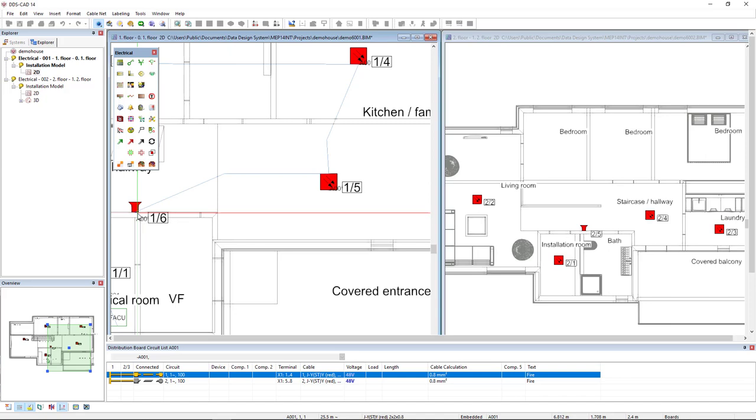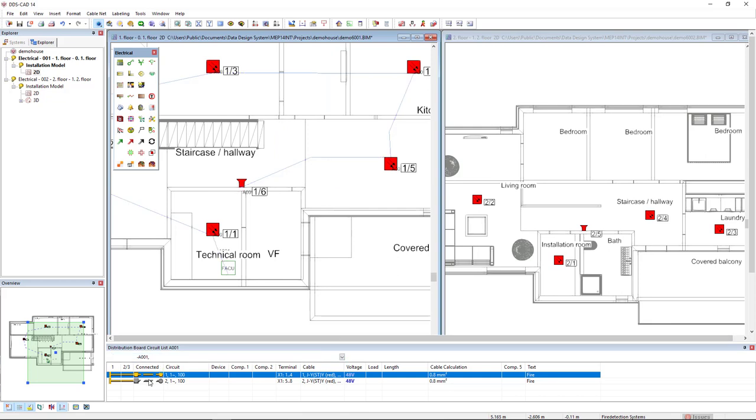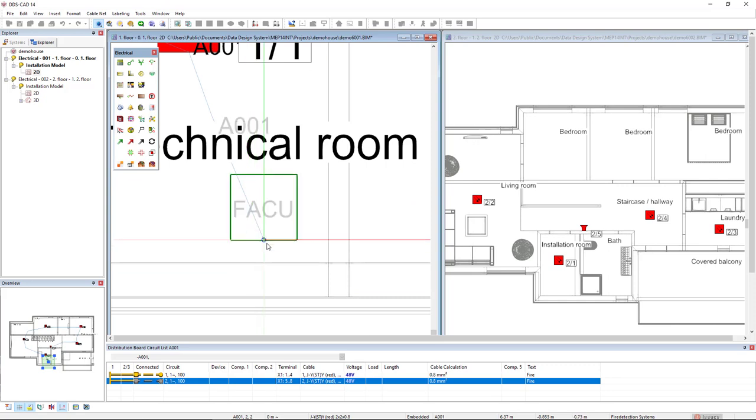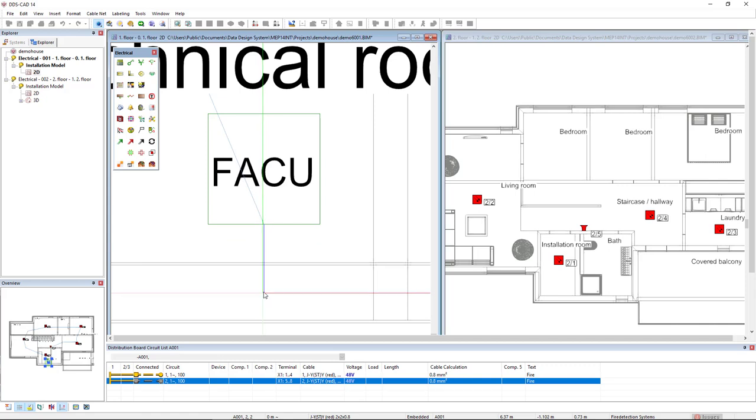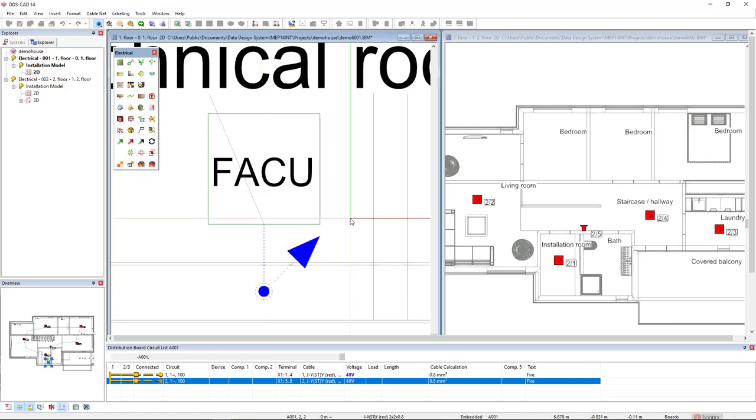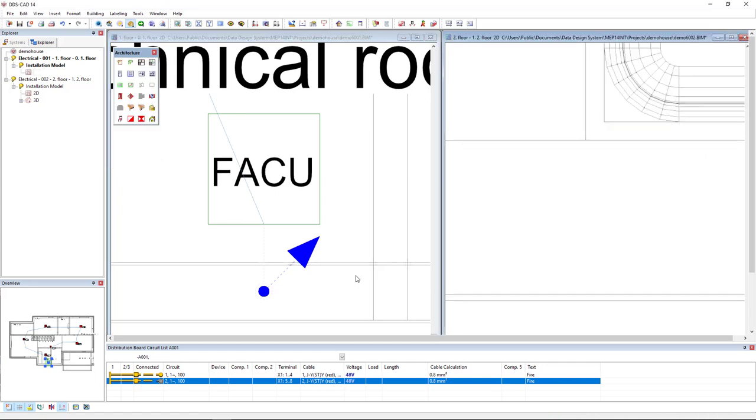Alright, so the first loop is connected. Now, I will press escape to close this function and start from the second circuit and draw cable again. Click OK to start with this cable and I will again connect to the board and I'm going into the wall to access the second floor. I will click on the context menu and I will select the option any story above. A symbol is created showing that this cable is connected to the floor above.